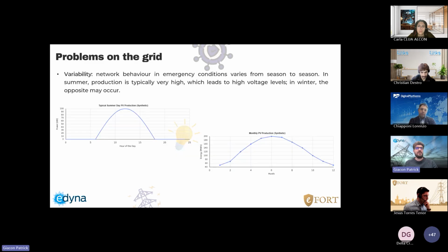Another important challenge is network variability. The behavior of the grid can change significantly from season to season. For example, during summer months, electricity production by PV systems is often very high, which can lead to over voltage situations. On the other hand, in winter, higher loads combined with lower generation may result in the opposite effect.